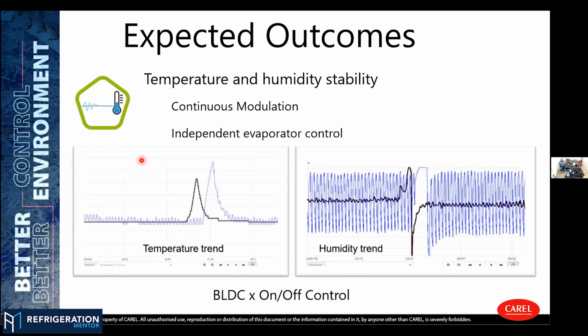But more than the temperature, the humidity will be very stable. Every time that you power cycle a unit, the humidity inside the ambient will change very much. So if you have a constant evaporation temperature, we could have a very constant humidity. For medium temperature application, where we have exposed product like vegetables, for example, it makes a lot of difference in terms of shelf life and the quality of the product. I definitely agree with that.